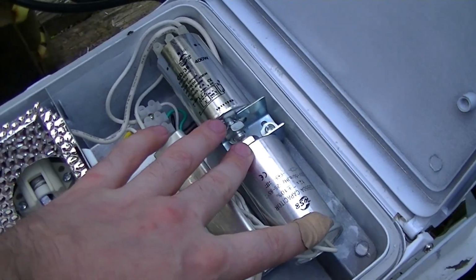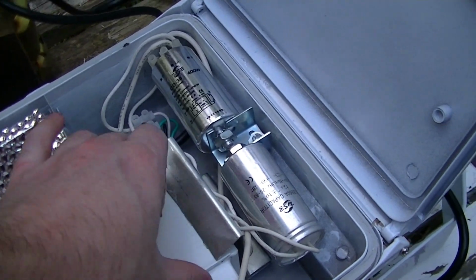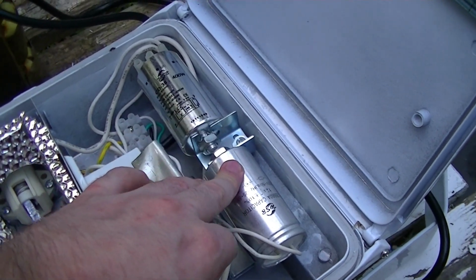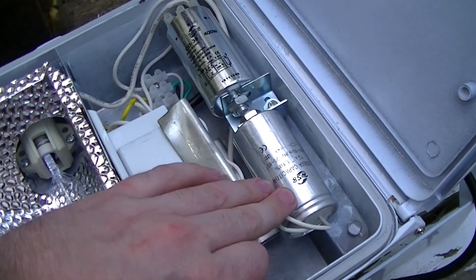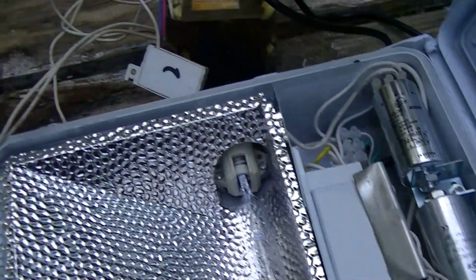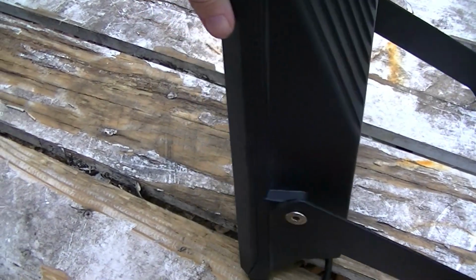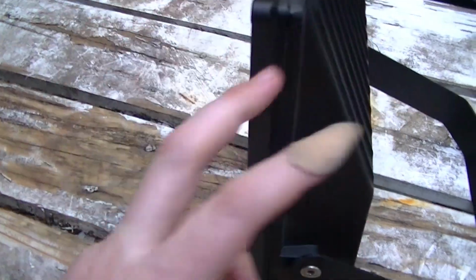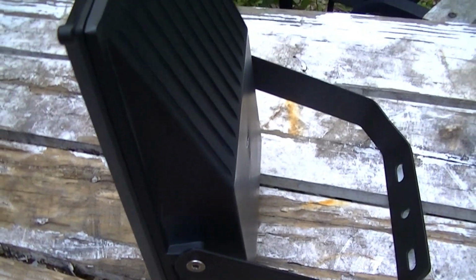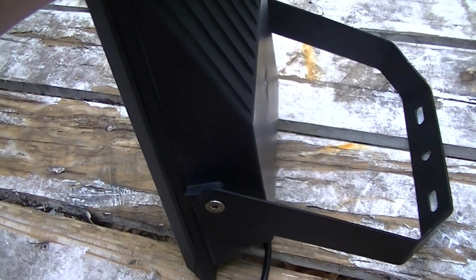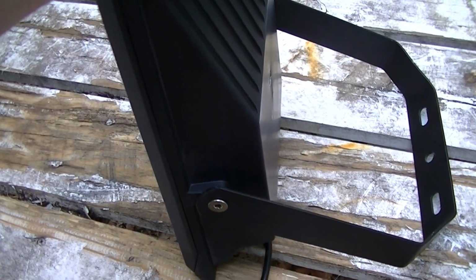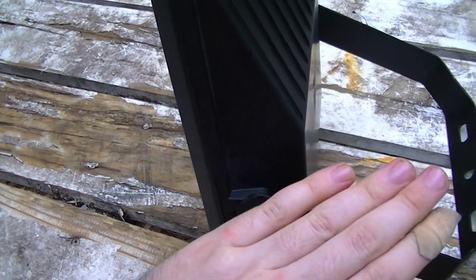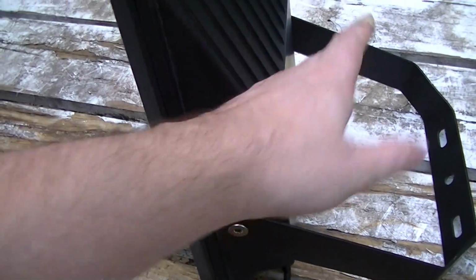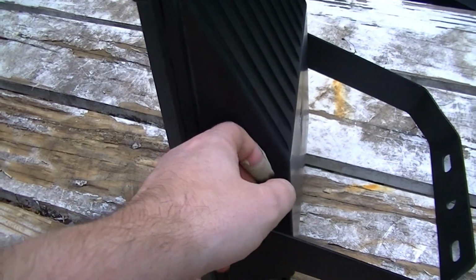And based on operating current of this fixture, because it's 150 watt, it would still have a fairly lagging power factor with this 12 microfarad capacitor. Because this is the other fixture which I just did a video on. This is 70 watt, quote unquote. And capacitor was damaged in shipping, so I replaced it with a 10 microfarad capacitor. Originally it also had a 12. And it had about a 98% power factor running on 220 volts at 50 cycles per second.